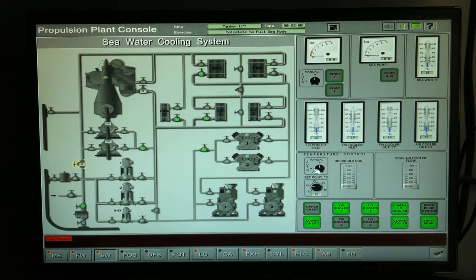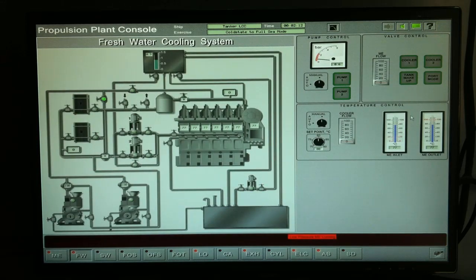Temperature controller set to auto. Start the pump, put it on auto. Freshwater system should be also running. Cooler number 1 open. Adjust main engine flow to around 60%. Start the pump, put it on auto. Temperature control to auto.